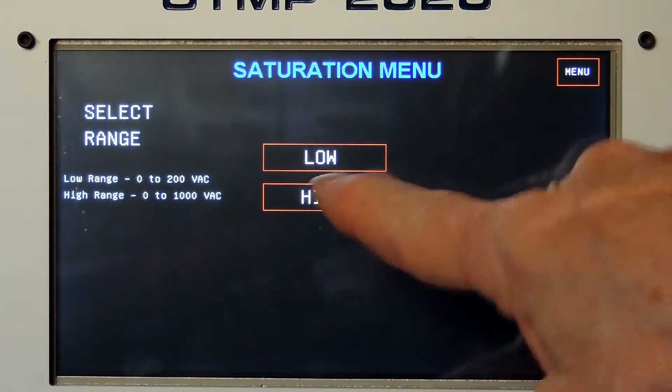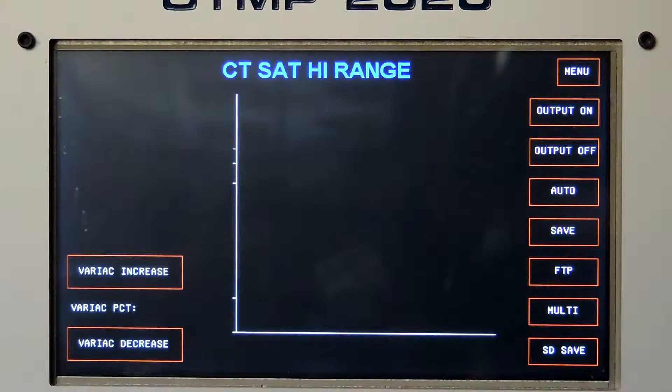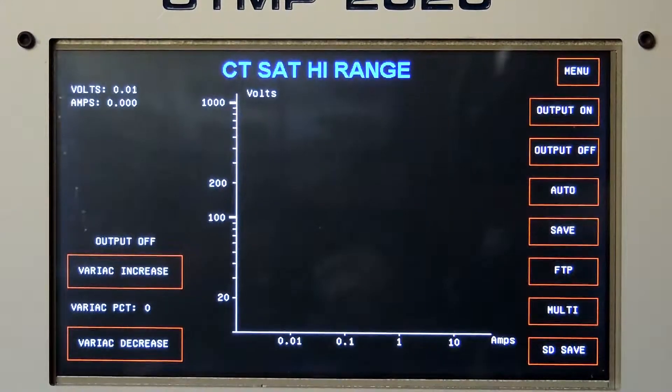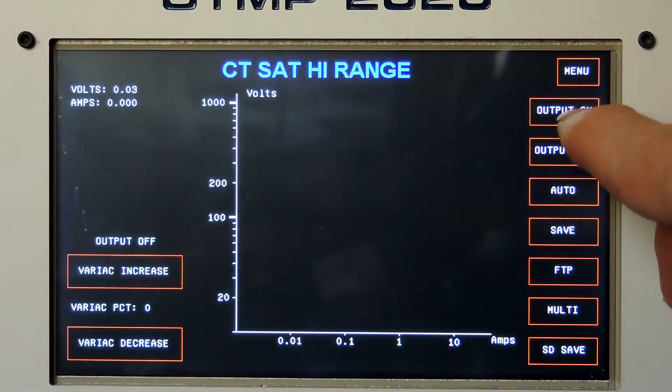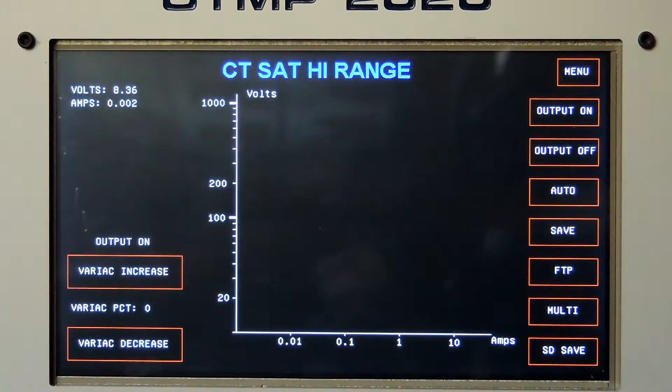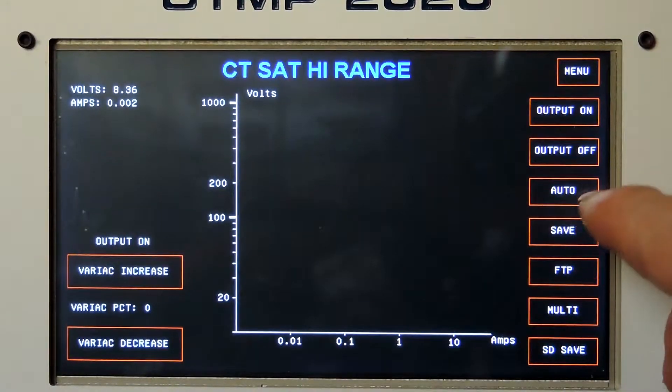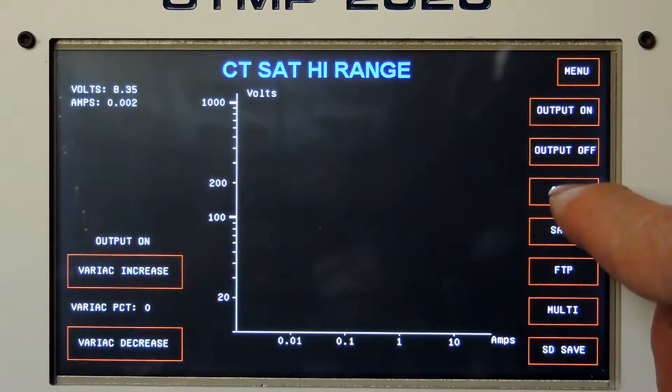I know this one saturates over 200 volts, so I'll select high range. Then all I have to do is turn the output on. I could do a manual test by raising and lowering the variac and recording the readings, but that makes it too difficult, so I'm just going to do the auto test.